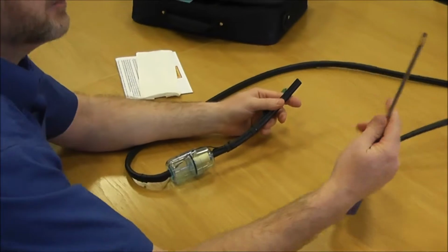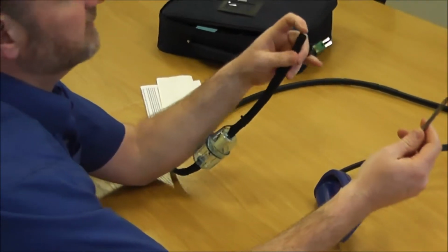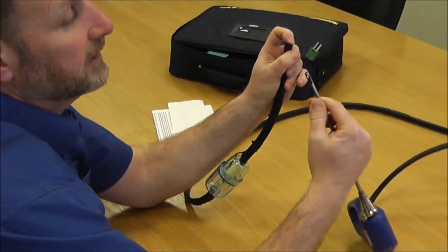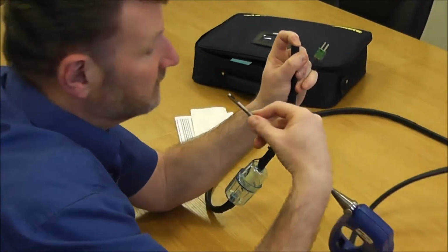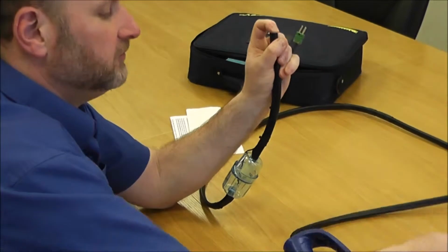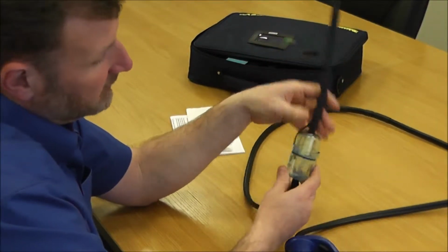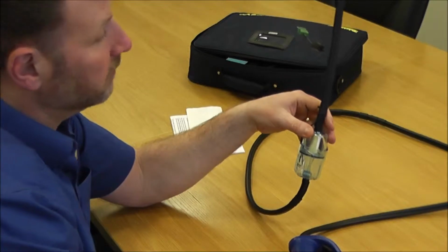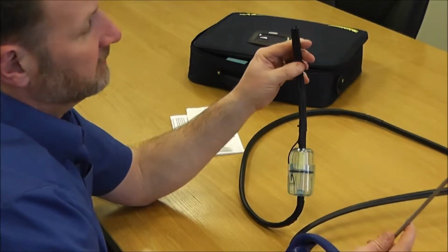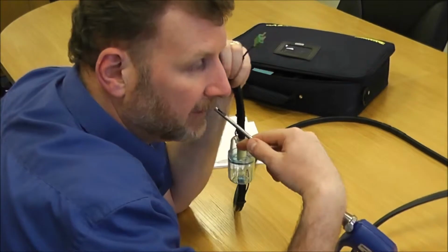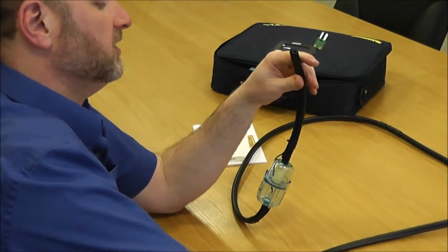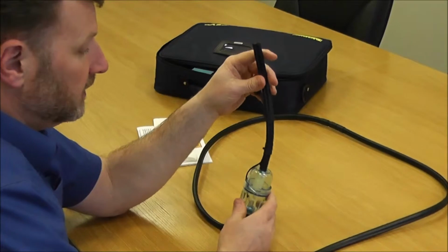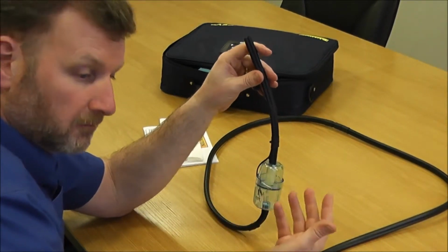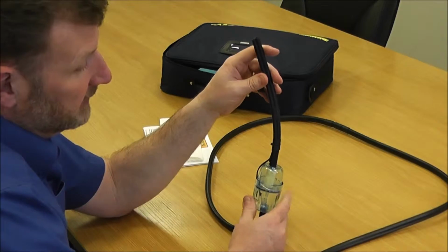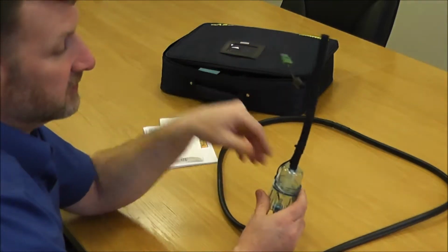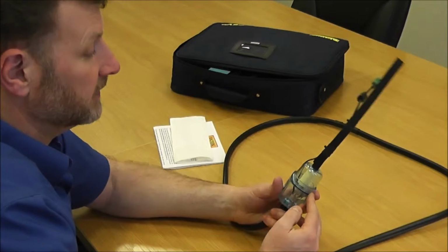firstly, if you get your probe and you put your finger over this end, block it up, and then blow down the metal work, encapsulating the end, obviously. What should happen is, if you can't blow down it, that shows the integrity of the line is okay and you've got no leaks anywhere along the way. If you repeat that test, but this time leave the open end and put it to your ear, blow down it, what that's showing you is you've got a clear line, you've got no blockages, and you can't hear any gurgling, so it means there's no moisture in the line. And then if it passes both those tests, then it's a good idea that the flue probe is working okay.